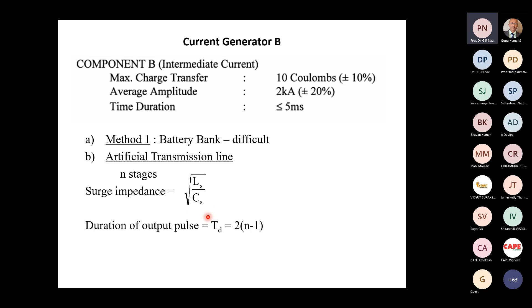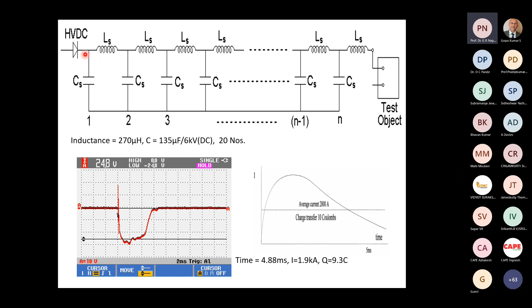We can generate a rectangular wave like this. This is a real wave shape that we have obtained, which meets all the requirements as per standards. In our case, each capacitance is 135 microfarads, two of them in parallel, that's 270 microfarads. This inductance of the order of 270 microhenries gives a surge impedance of 1 ohm. So if we charge it to 4 kV, we get an output current of about 2 kiloamperes.